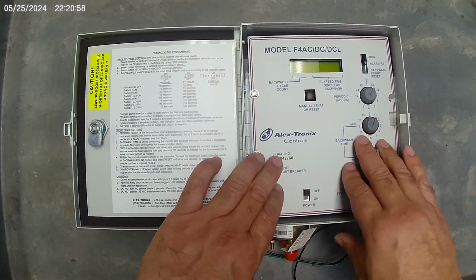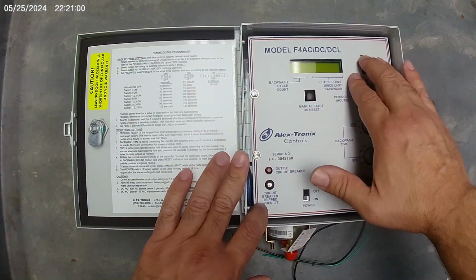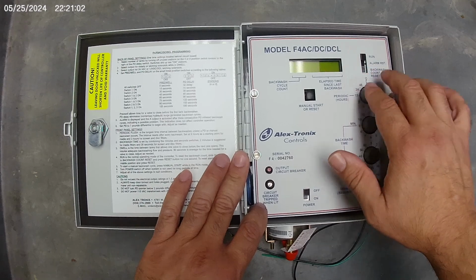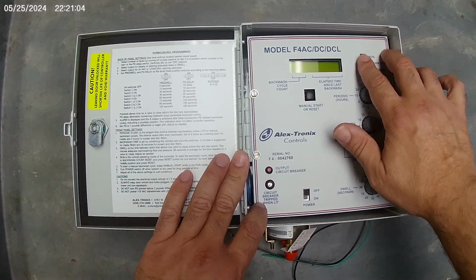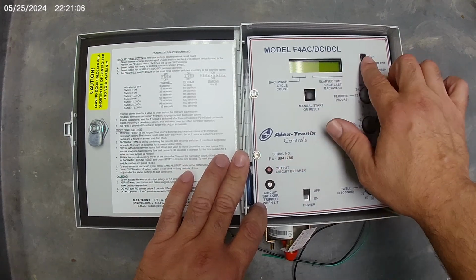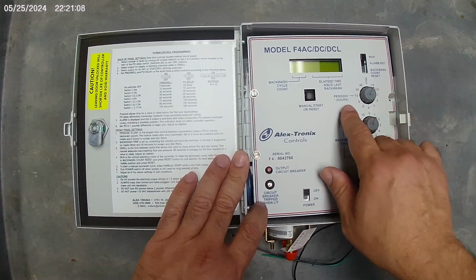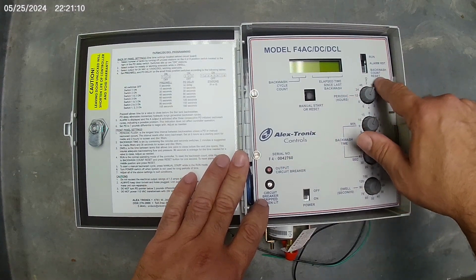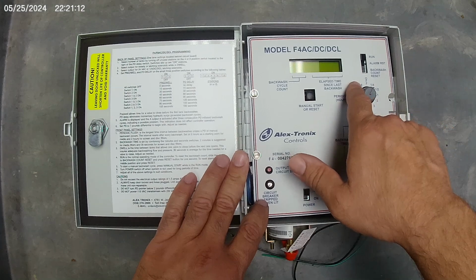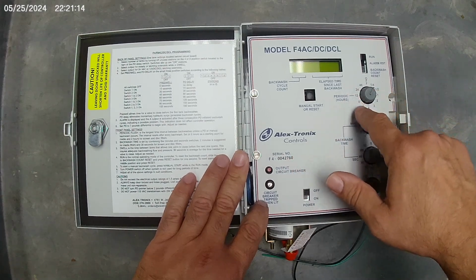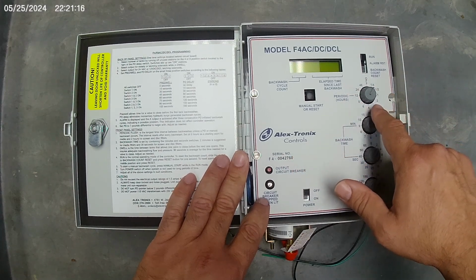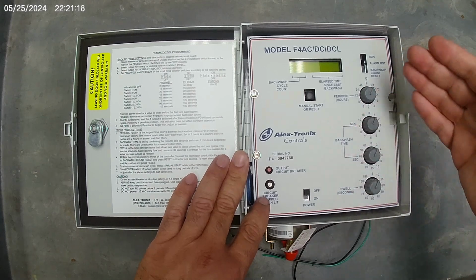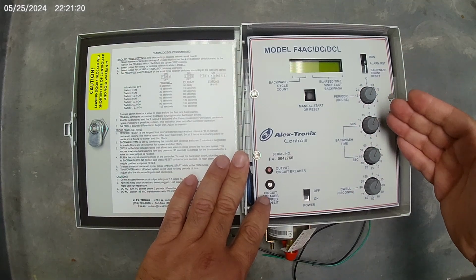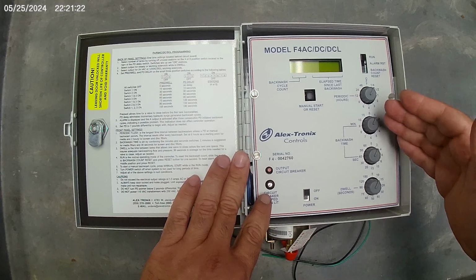The programming is pretty simple. We have a 3-position selector switch here, function switch. You want to make sure that's in the run position, otherwise you're locked out of starting a flush. Periodic is adjustable from 15 minutes up to 48 hours, and that will be set based on the quality of your water or how often you want to turn the filters over, regardless of the pressure loss across them.